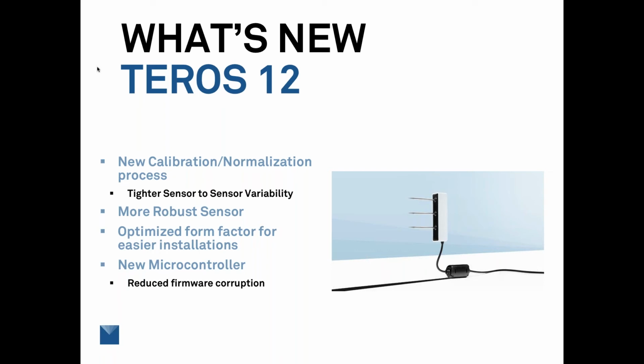We also wanted to improve the sensor-to-sensor variability. Traditionally, what we've done with soil moisture sensors is calibrate them using liquid dielectric standards in our production facility, but those are a little hard to work with and not quite as tight in reproducibility as we'd like to see. So we had a goal of moving to a new calibration process using electronic calibration with different levels of capacitance. We moved towards that new process in production with the TEROS 12, and that's really helped improve sensor-to-sensor variability. It's also streamlined the calibration process, allowing us to bring the cost down. So overall, it's an improvement for the customer in terms of both performance and price.